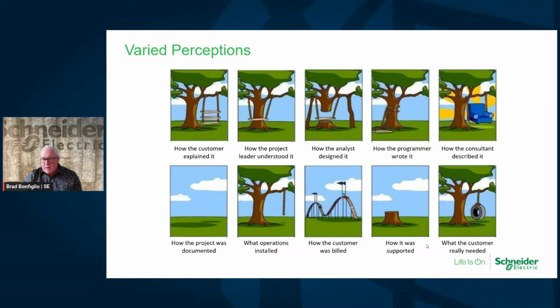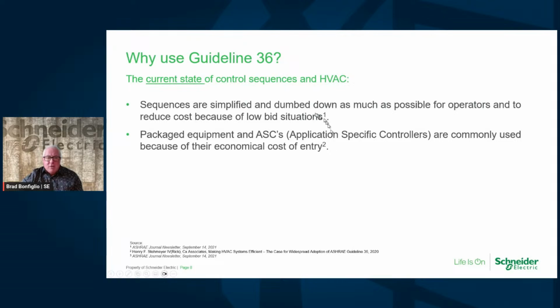So again, there's no wrong in this. It's just faults of perceptions of one group to another and what you really needed as an end result. So hence, this is what the sequences are trying to do in the standardization. So why use it? Because the current state of the control systems is they're typically dumbed down to make it simple. A lot of times that's to reduce cost, and especially we want to make sure we get a low bid situation. We want to keep our costs down, so we want to make it as simple as possible.